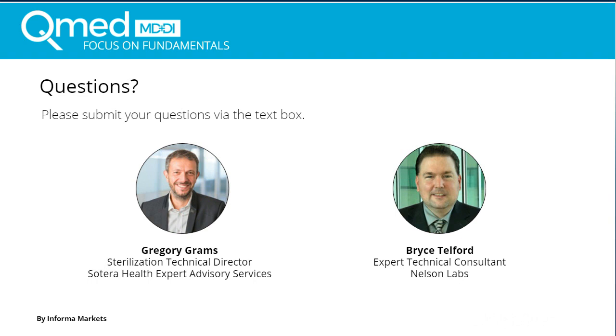So we are recommending, in terms of reproducibility and repeatability, a minimum of 3 samples tested by time point, so that we have at least the bare minimum statistical relevance. But today there is no regulation forcing you to select a sample size, and I would say 3 is good practice, because you can assess whether or not you have an outlier in your testing and if it's robust enough.